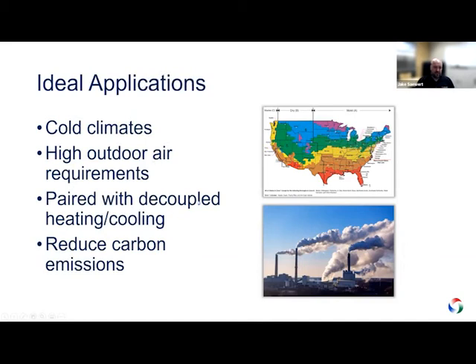Obviously, high outdoor air requirements. It's very, very good when you pair it with a decoupled system like a VRF system or water source heat pumps or some other decoupled mode of heating and cooling. And then as we start to see more and more of a push for electrification and reducing carbon emissions, this can really cut down on the amount of heat that you need in winter.